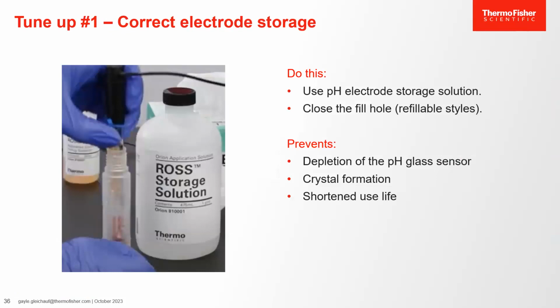Tune-up number 1, correct electrode storage. Use a specialized pH electrode storage solution and close the fill hole before storage. This prevents depletion of the glass pH sensor, crystals clogging the junction, and a shortened use life.